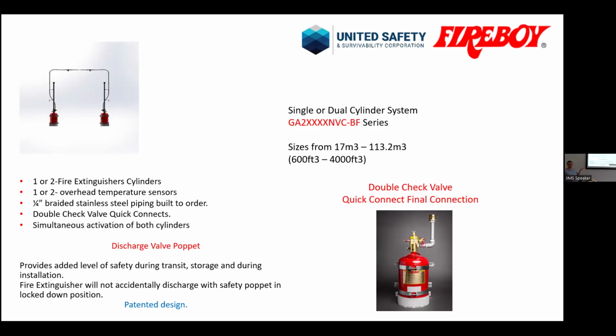So the difference is that the GA system using FK5112 can protect space up to 2,000 cubic feet with a single cylinder, or a dual system, which is connected, can protect up to 4,000 cubic feet. Now, the dual system is connected with something we call a GA link. It's a stainless steel hose with 2 thermal sensors that connect the 2 cylinders together. Now, this can be placed inside or outside of the protected space. Most of the time it will be inside, but this is the only time you can have 2 cylinders fitted within one space, because it allows for simultaneous discharge within 10 seconds.